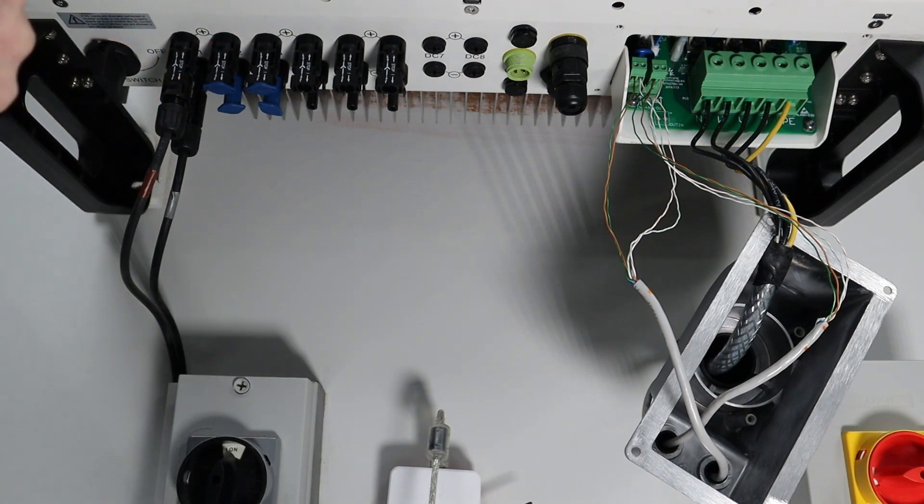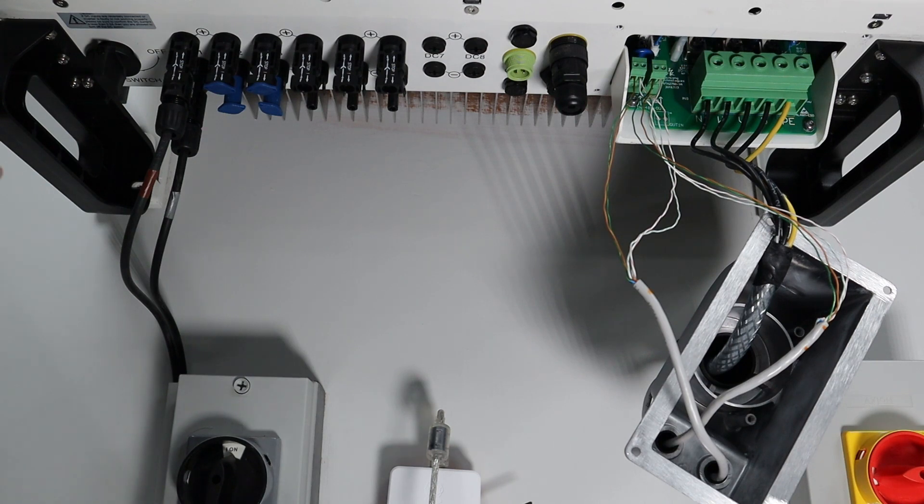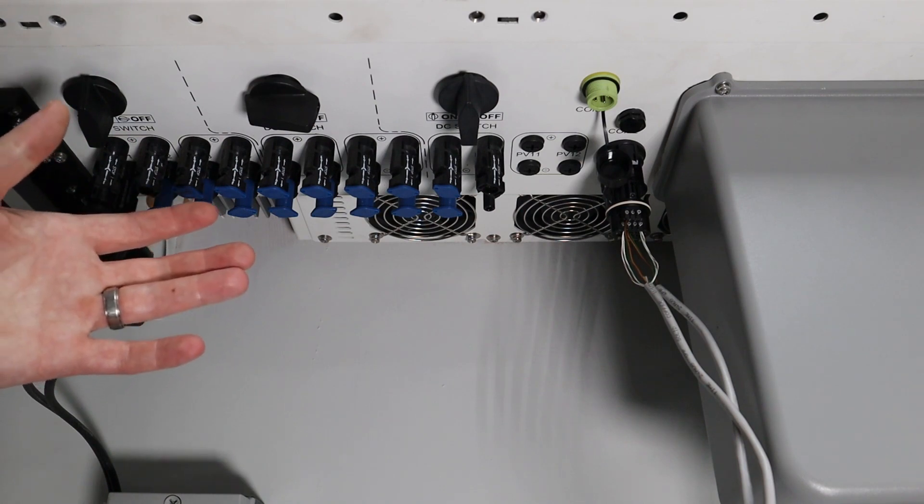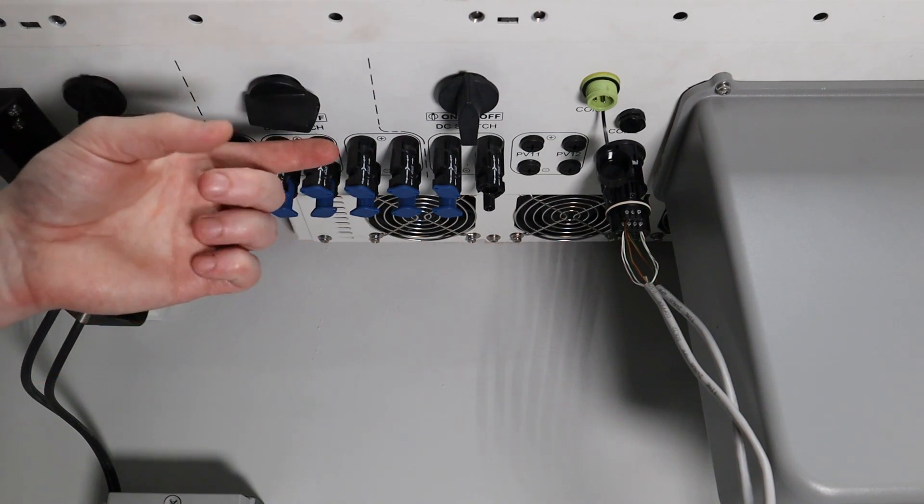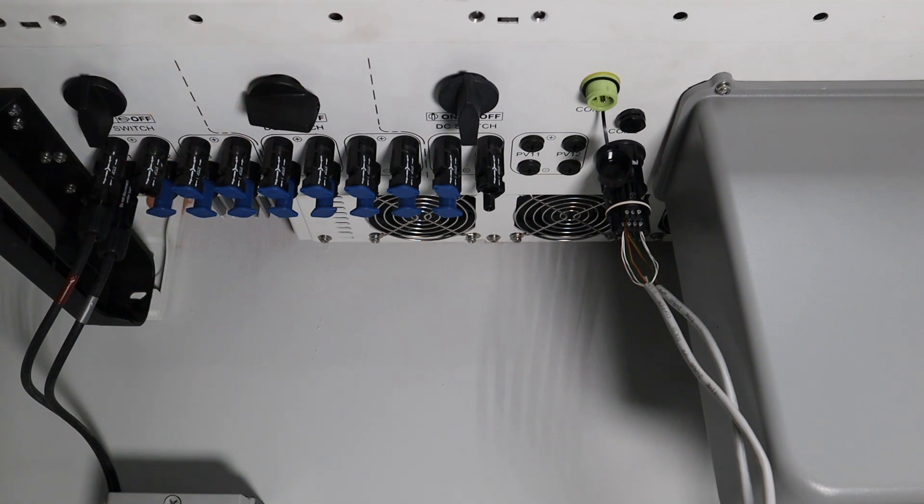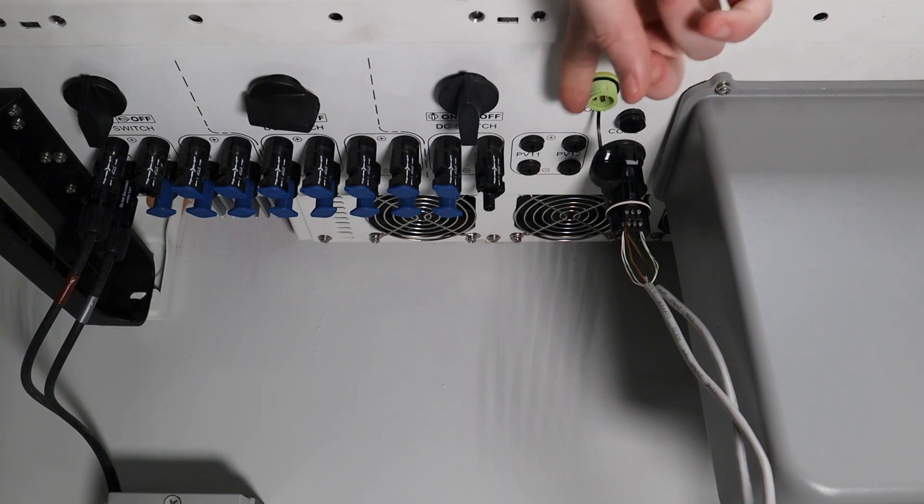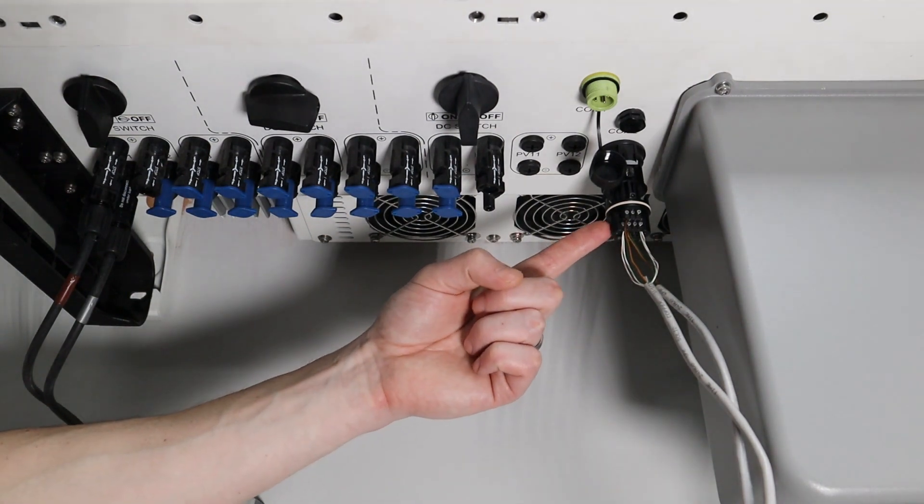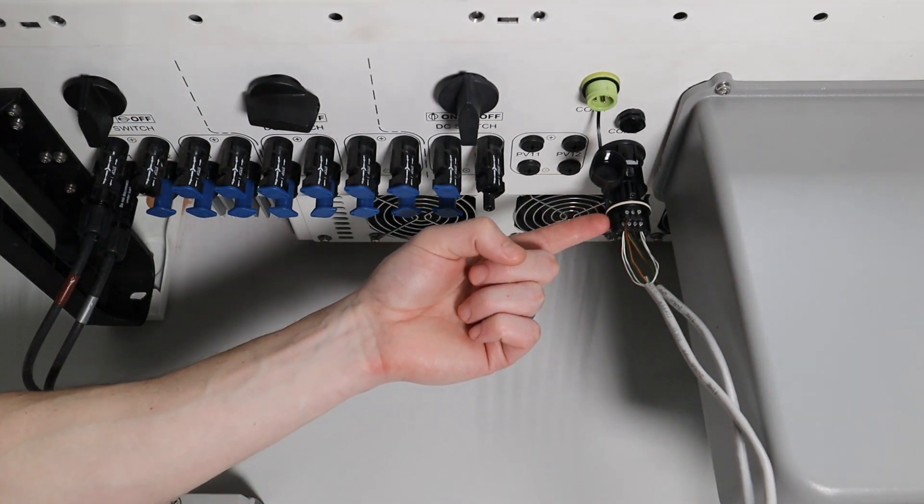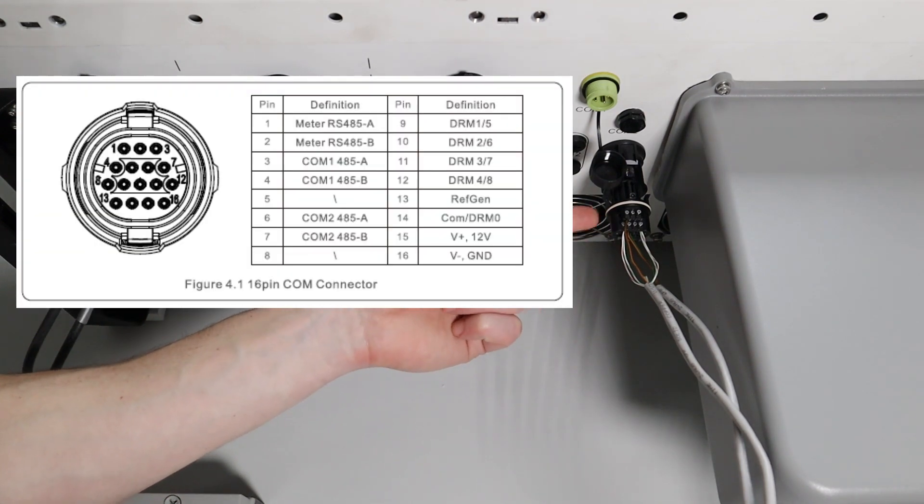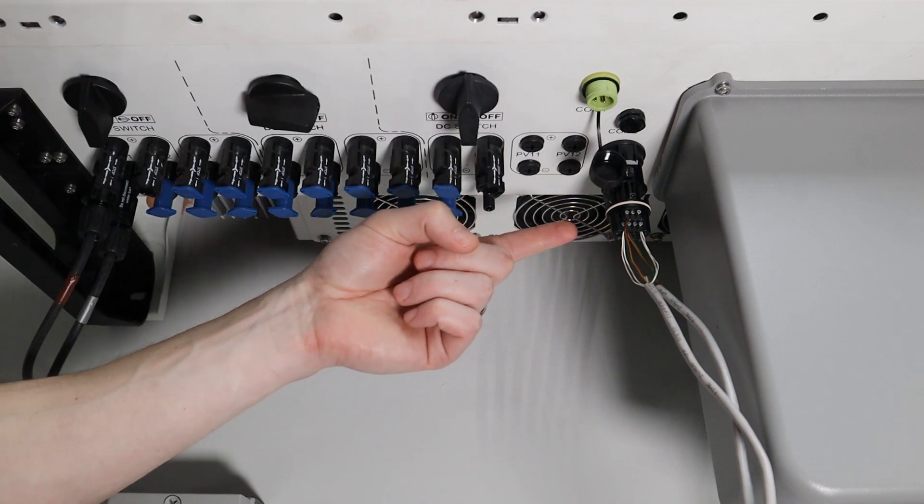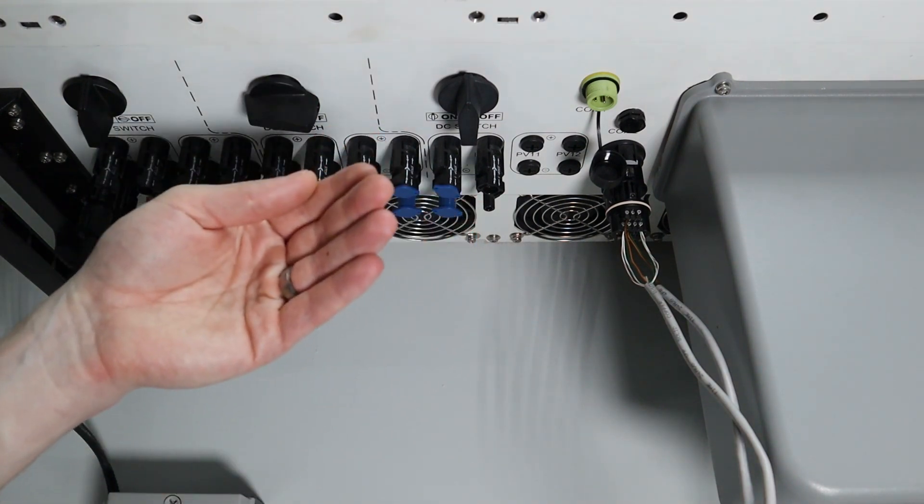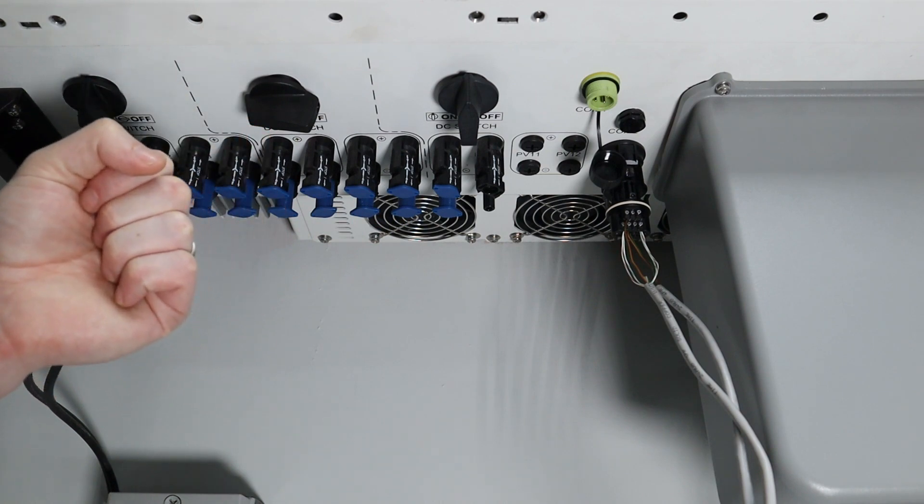You've also got options like RJ45s on this inverter. And then on the next inverter, I'm going to look at, we've got the 16 pin plug, which you can also use to connect into the network. Okay, I'm at the final inverter that we're going to look at, or the final inverter in our EPM control. And here we've still got that same port for COM port 1, the green 4 pin plug, which you can set up and just shoot out a blue and shoot out a yellow and connect it through, like I described. And then you've also got this option of a 16 pin plug. So there's two RS-485s in and out on this plug. And you'll see on the screen now, the pin outs for this plug. And you can use this just like you used the screw terminal block. And you get this onto the network. And then once you've addressed the inverters accordingly, it should be all seen by the EPM. And this inverter should be able to be controlled by the EPM.